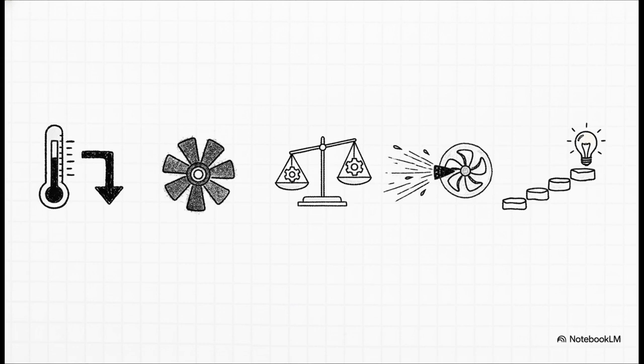All right, let's bring it all together. If you take away anything from this explainer today, memorize these 5 non-negotiable numbers for your field guide. First, turbine derating. Expect a 0.5 to 0.8% power loss for every degree Celsius above ISO. Second, the dirty engine factor. Always account for a minus 5% power drop. Third, droop governing. The standard is 4 to 5%. Fourth, compressor wash. Mandated every 500 to 1,000 hours. And fifth, commissioning. Always follow the 5-step sequence.